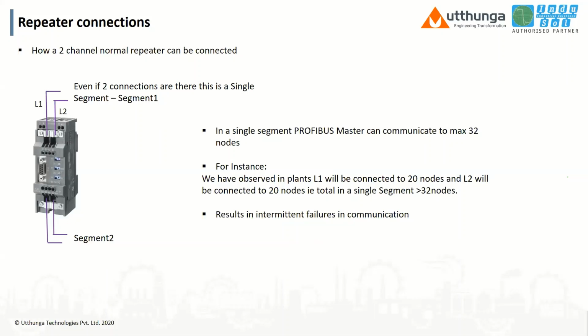So this is what we have at repeater connections. How is the repeater connection? When I was visiting a lot of plants, I saw that repeater connections were not in the proper standard way. You can see here, this is a 2-channel repeater. Most people think L1 is one segment and L2 is another segment, but L1 and L2 are a single segment. And the down part, you can also see 2 lines. That's another segment. So there are only 2 segments in this repeater. There are no 4 segments. If you connect L1 and L2 to 2 lines also, it is communicating on the same line, like a single segment.